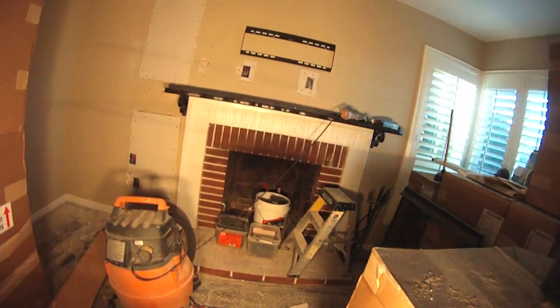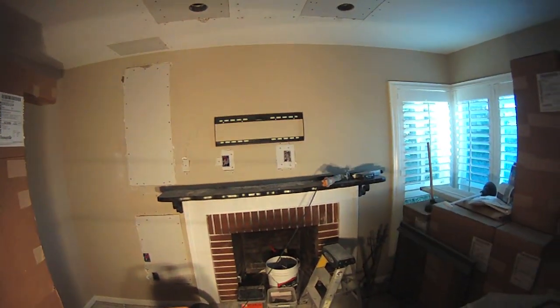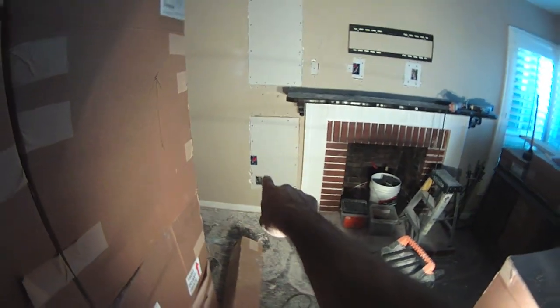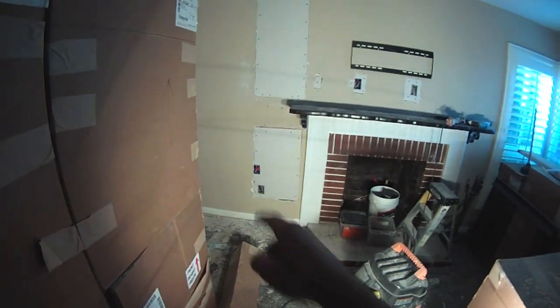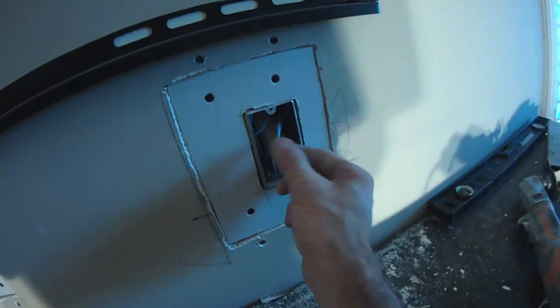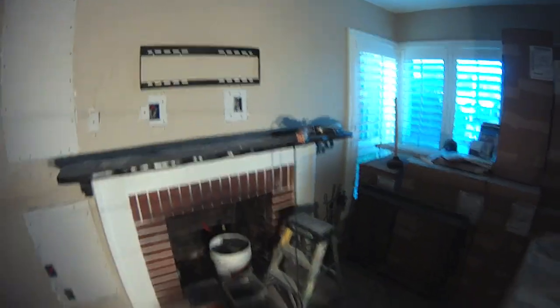This box on the right-hand side — the silver metal one — has two-inch aluminum flexible conduit. It's not cheap, but that's the way to do it. It's basically going to be a cable chase; it goes back around behind the wall and drops down to that lower box. In that lower box there's a double gang box — both of these are double gang boxes — and I put a single gang mud ring around it. This bottom one has the CAT5 wiring and the RG6, plus two nylon pull strings I ran through there, so when the cable or dish box gets installed they can run cables up to the TV.